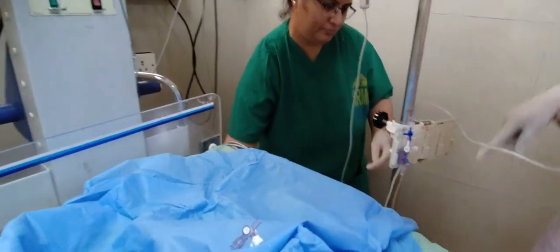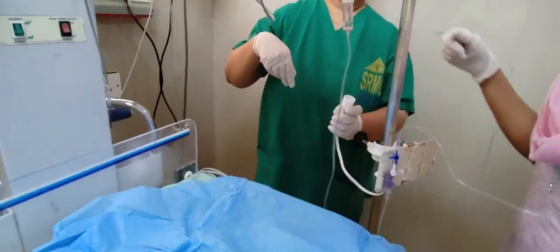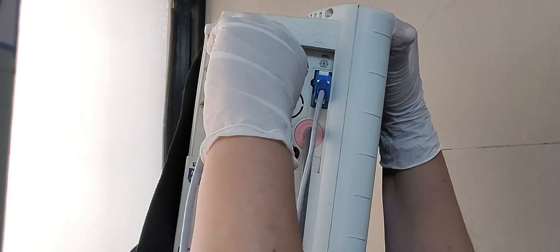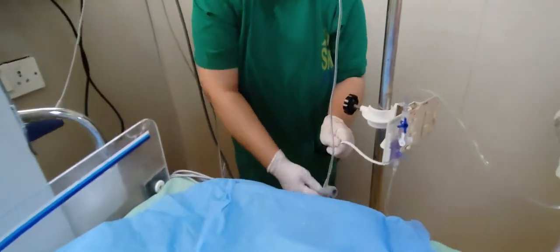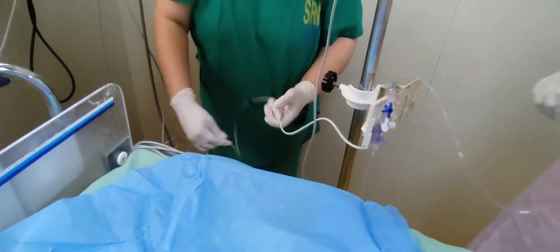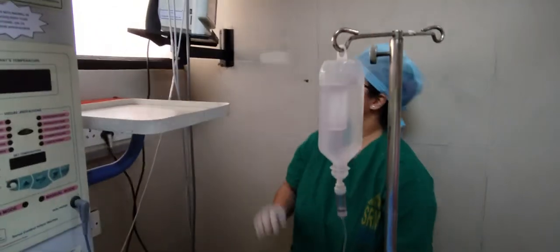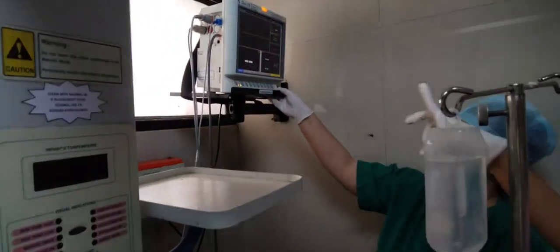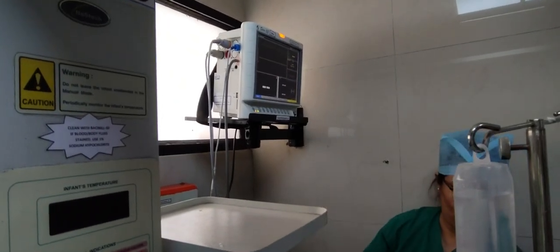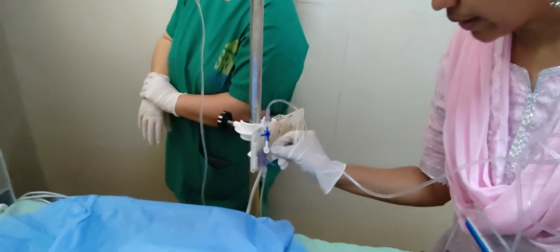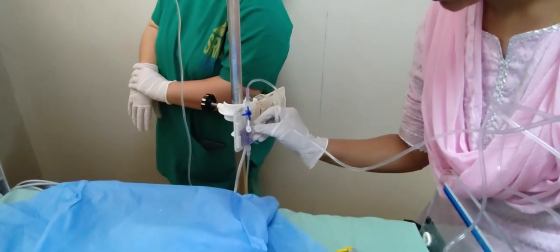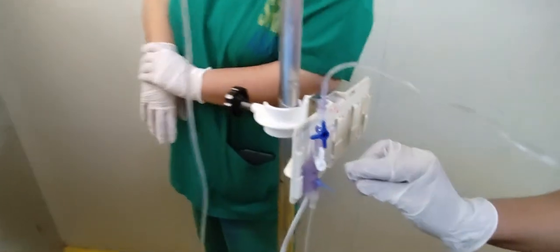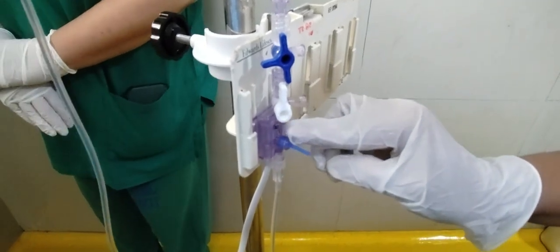So the next thing is to connect the cable. Please connect to the multi-parameter monitor. So she is connecting it to one of the IBP ports and the other end to the cable of the transducer device. Okay. So the next process would be to do the zeroing. Once it is connected, it would have got activated. So now I need to open it to atmosphere, and I make sure that I maintain the sterility. So here it is closed to the baby side and open to the atmosphere. So from the pressure transducer, this is open to the atmosphere.